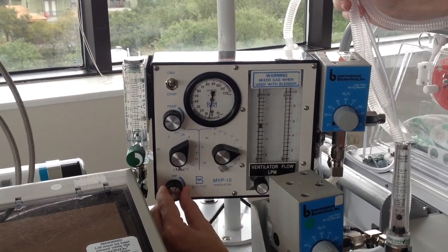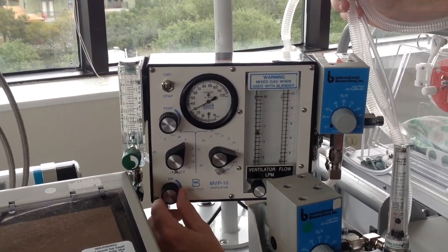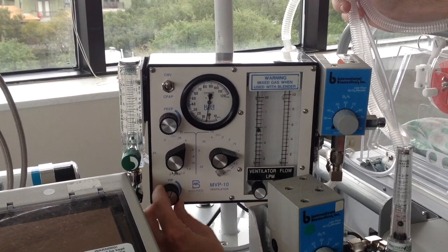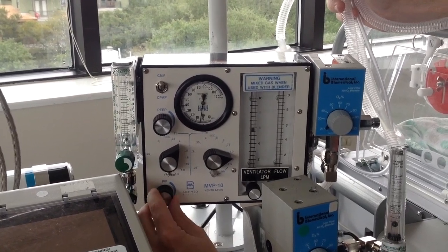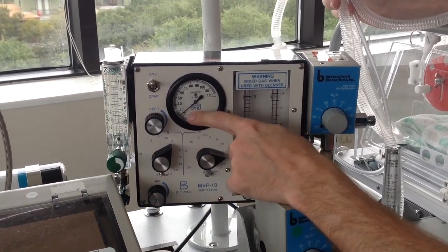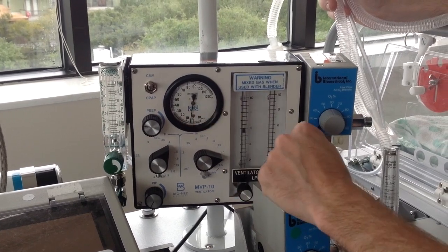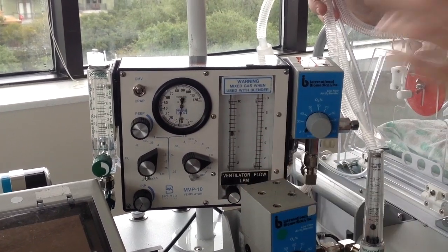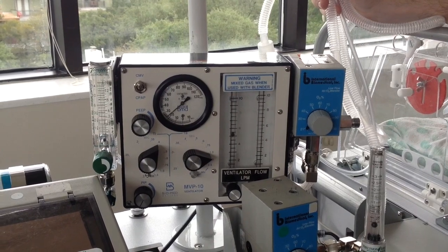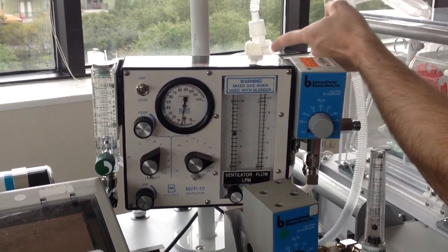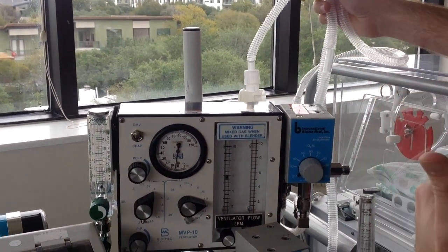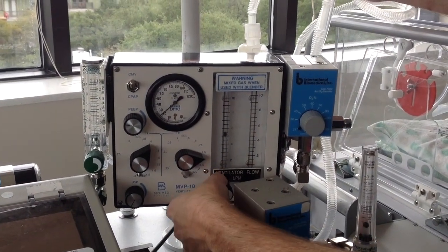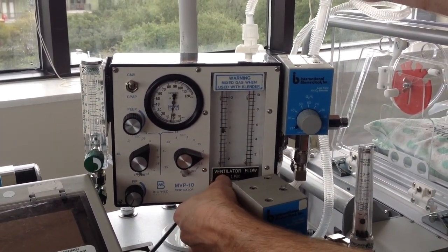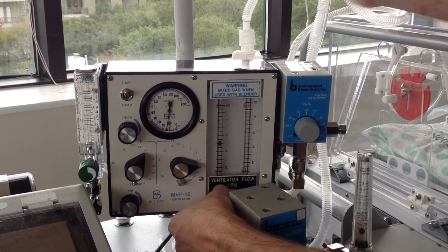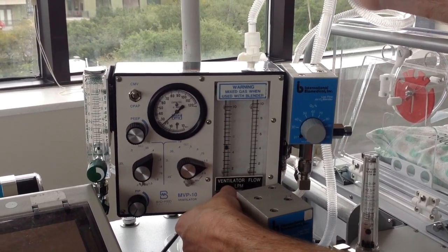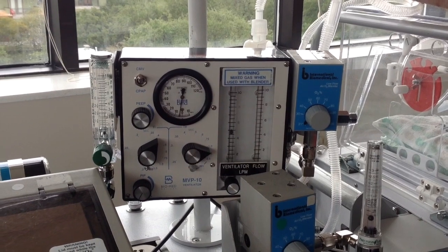Now, if I decrease my PIP, I'm tightening up my limit to where I'm going to trim off part of this breath. Hear that? So now I'm at about 24 or so. And you hear that screeching sound? That's because the flow is pushing against this expiratory valve right here. So one way to get rid of that screeching is to decrease your flow. That might be an indication that your flow is a little too high for the settings you're trying to get.